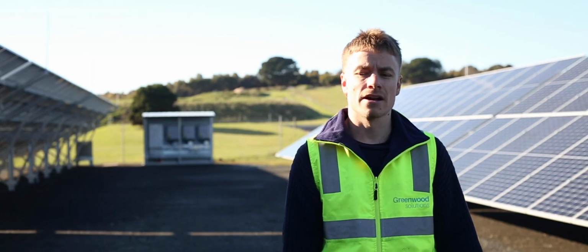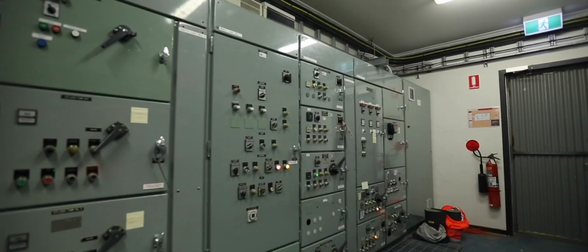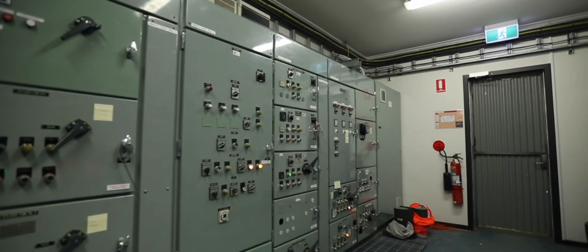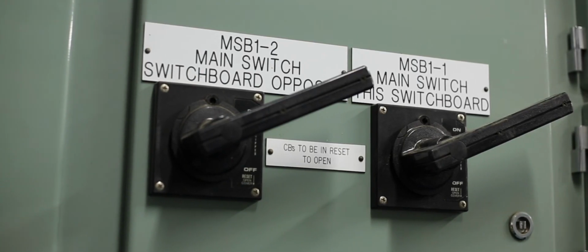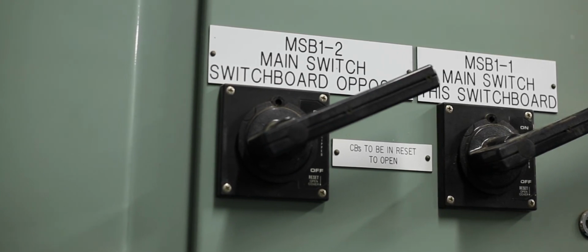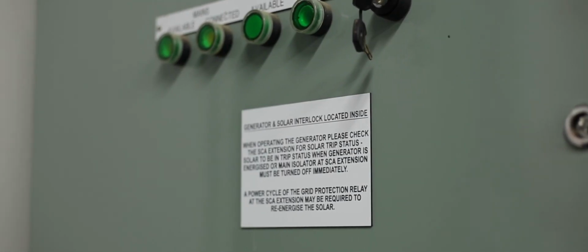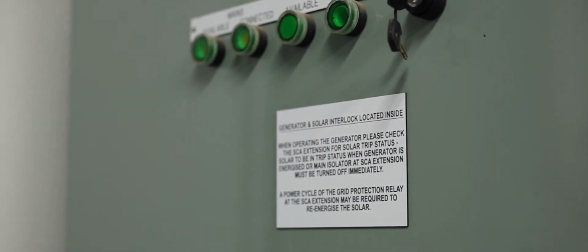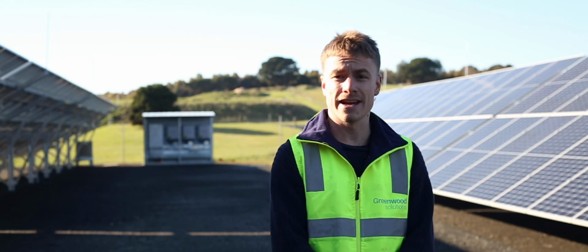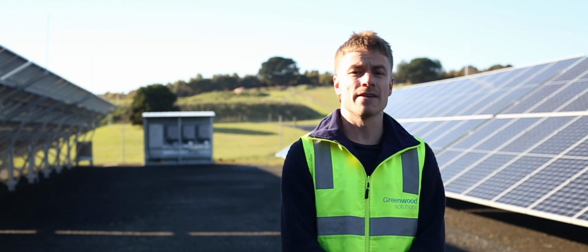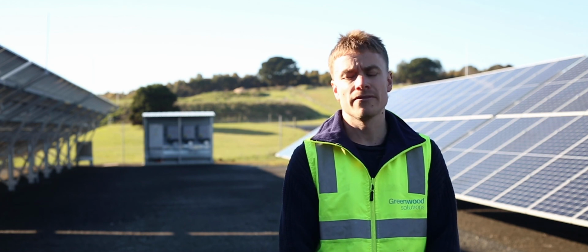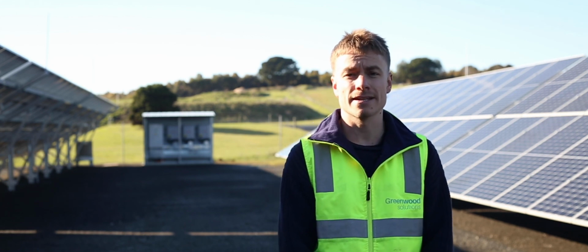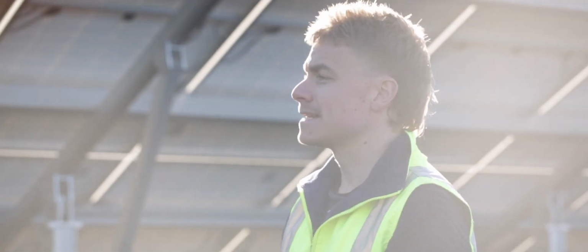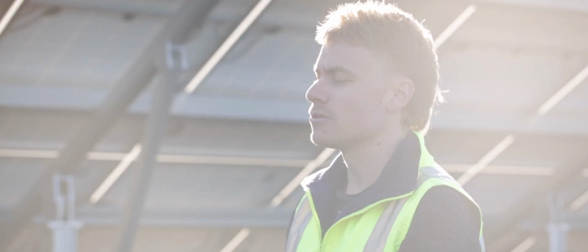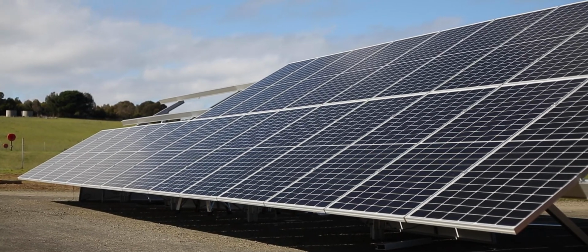The array is about 110 metres from the SCA extension, which is a distribution board which connects into the main switchboard. That main switchboard also has a generator, as this is an essential service to the community. It needs backup power. So the power is generated out here at the array and then fed back into the inverters underground, from the inverters into a PVDB and underground AC cabling for 110 metres to the SCA extension where the protection relay is.